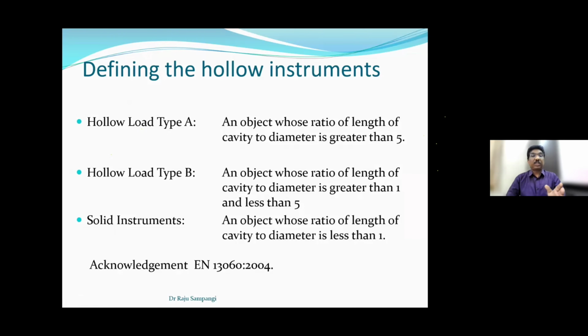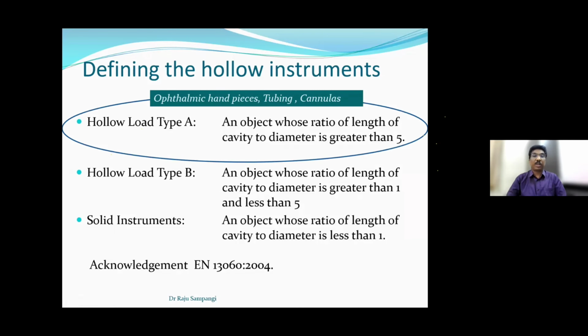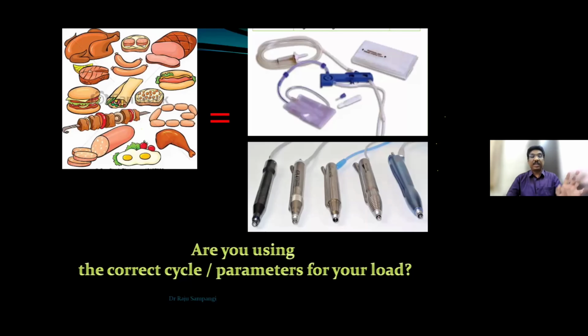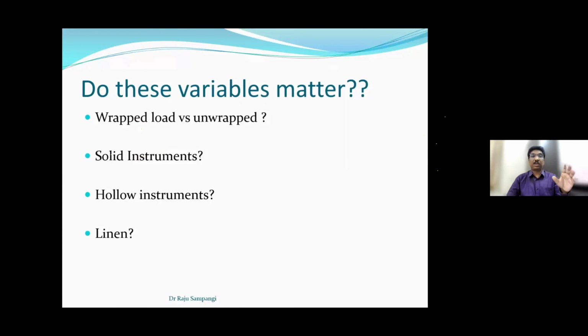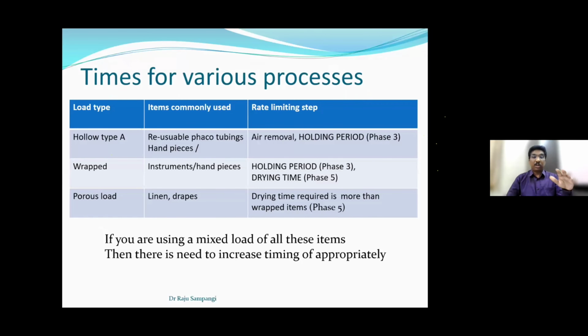Again, coming to the hollow instruments, you have type A hollow loads. This is what we commonly use in ophthalmic instruments. So what I mean to say is the instruments that we are using, like the phaco handpieces and tubings, are similar to the meat. So you need to use the correct parameters to sterilize these instruments. Then depending on the other variables, you have wrapped or unwrapped, whether it's hollow instruments or linen. It's also important to understand when you're using different types of loads within the same load, like different types of instruments, then you have to change accordingly. Suppose you are using a wrapped cycle, then your holding time will increase, and so will your drying time.